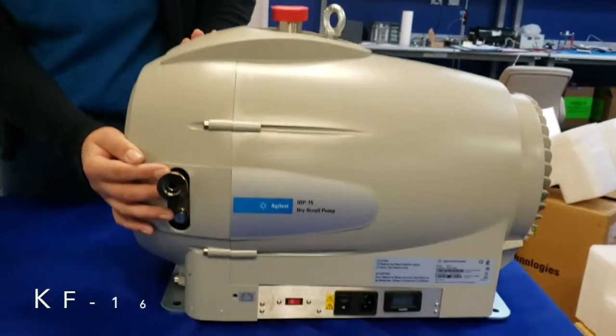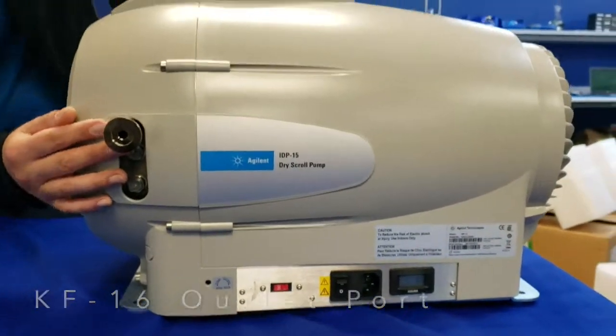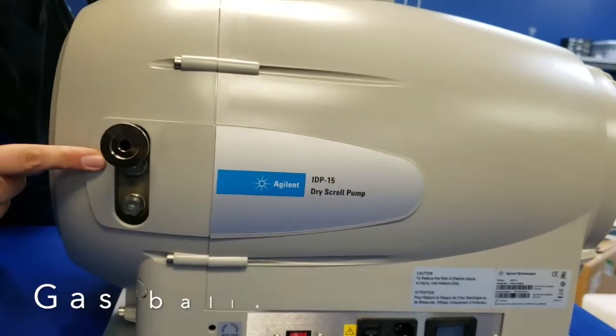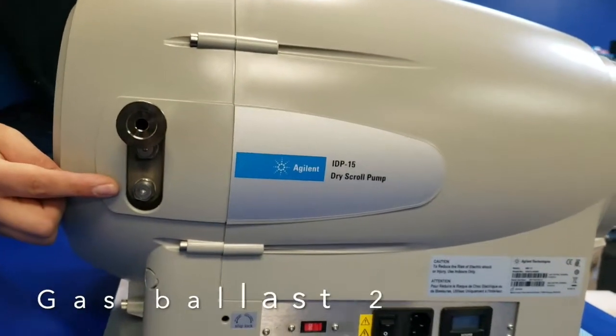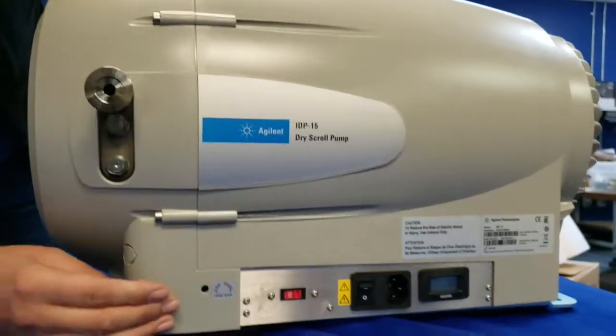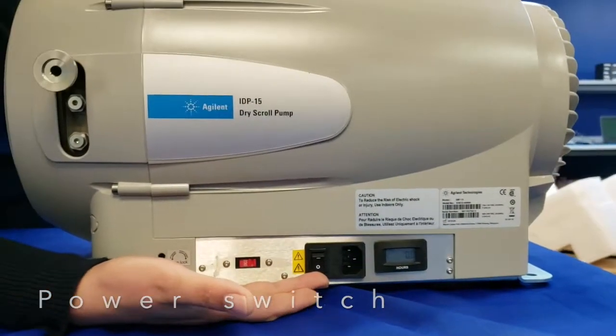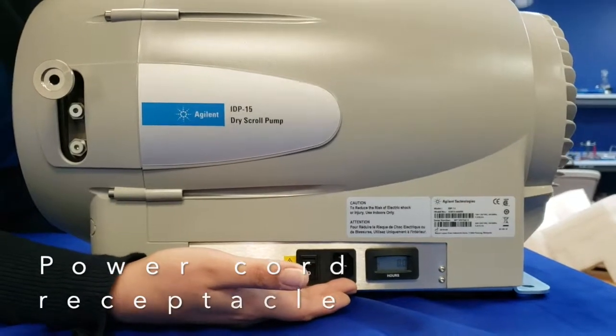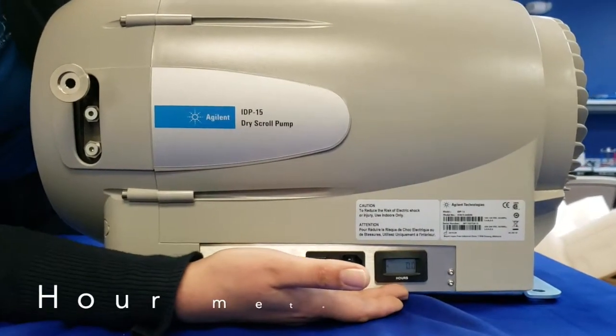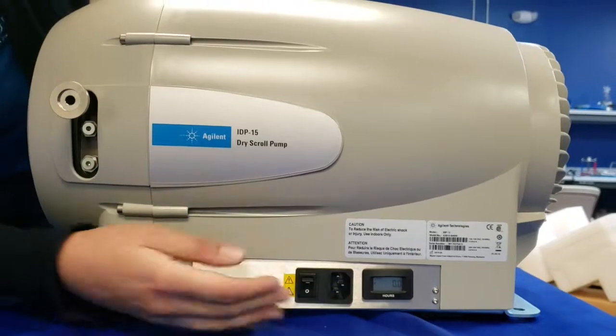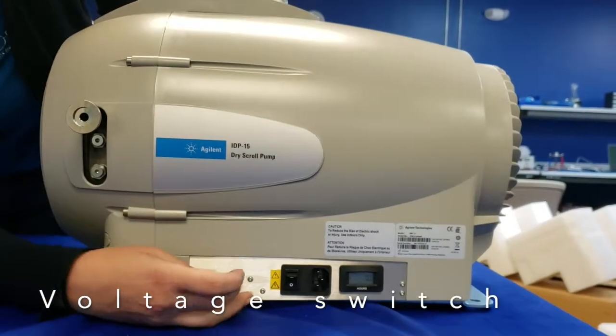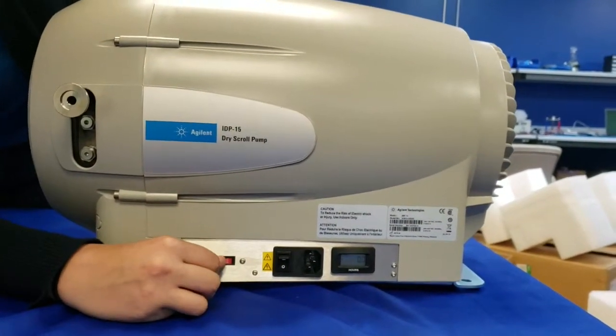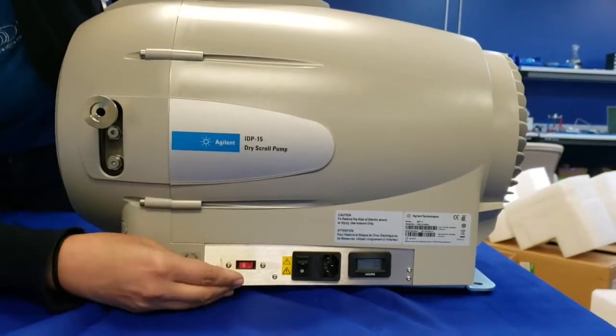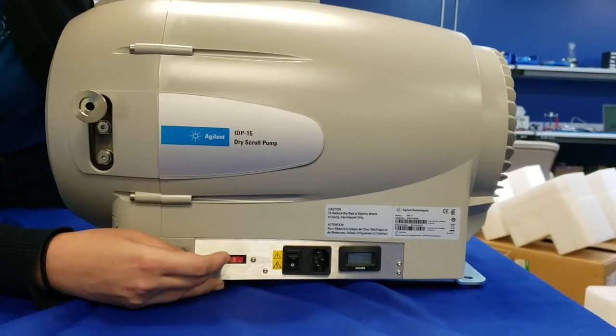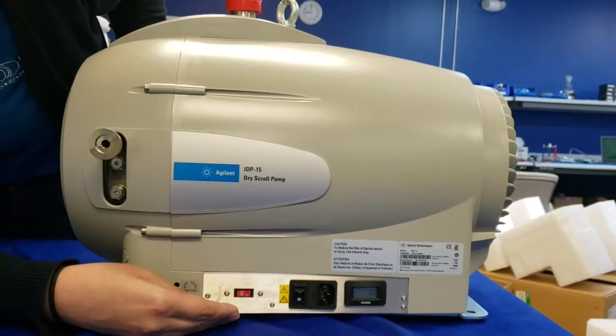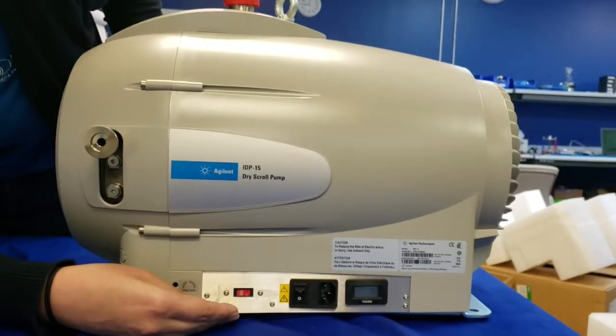Next is the KF16 outlet port, along with the ports for gas ballast 1 and gas ballast 2. There's the on and off power switch, the receptacle for the power cord, and the hour meter to show how long your pump has been running, and the voltage selector switch, which allows the user to change from 230 volts to 115 volts. The pump comes preset at 230 volts from the factory, so check your voltage requirements before powering on.